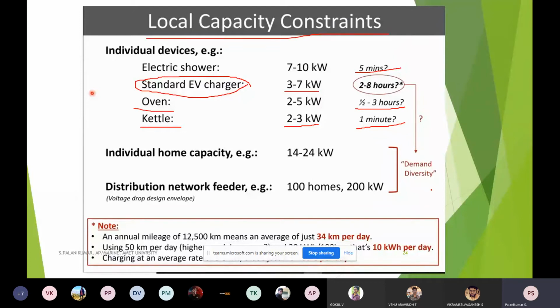That's why I told you - suppose I'm having a distributed network for 100 homes, if a 200 kVA transformer is there. Assuming power factor is nearer to 1, so 200 kilowatt of power we need for 100 homes. So individual home capacity is 14 to 24 kilowatt.